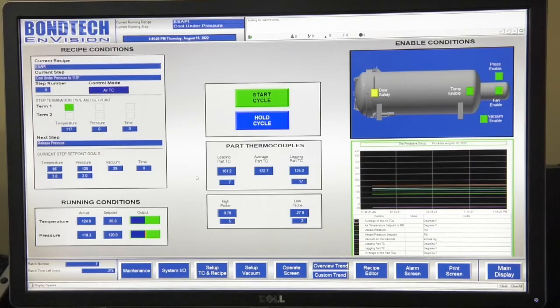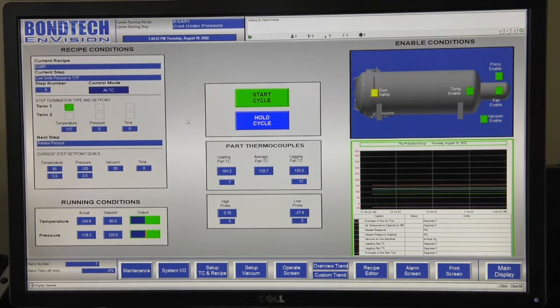The operate screen is actually the main screen of the system, and this is what most of the users will use. Here you can actually see what current recipe is being shown based on the product that is being used at that time, and what step you are at along that process in that cycle. It also tells you what the termination set point is for each individual item, whether it be the temperature set point, pressure, or time, and then what the next step to follow will be.